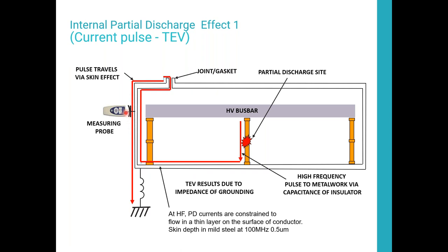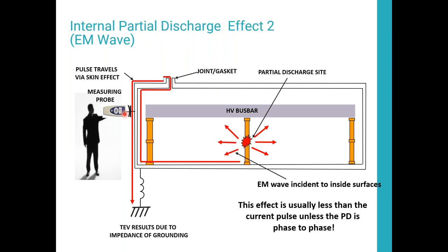What we found was, if you capacitively couple to the surface of the metal, you're able to measure those current pulses as a voltage pulse, a voltage amplitude. That's what we're looking for, using a capacitive coupled voltmeter. It's a specialized meter, and by holding it you're making a capacitive coupled path to ground. In reality, we're looking at a couple hundred millivolts, maybe 1 or 2 volts, so you're not exposing yourself to high voltages. It's not a safety issue.